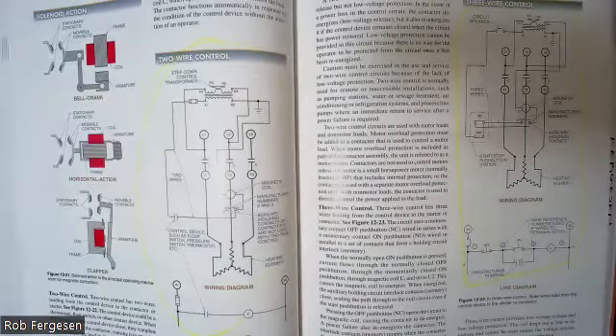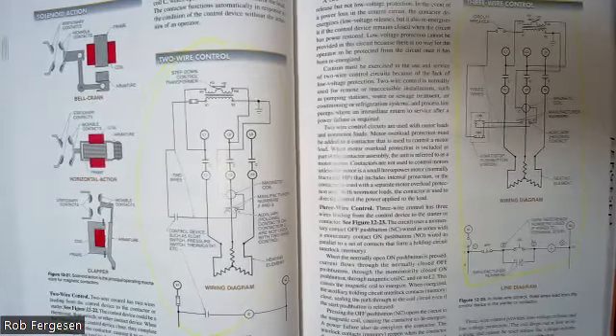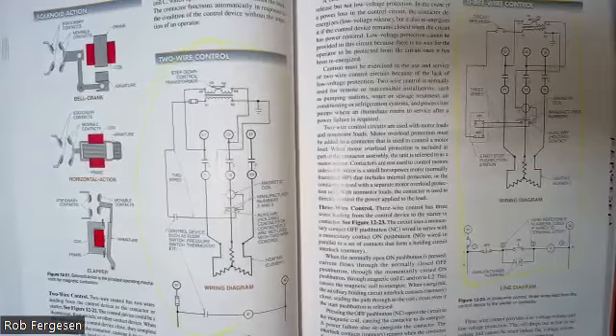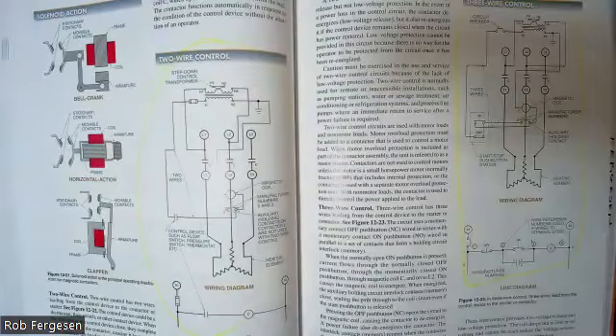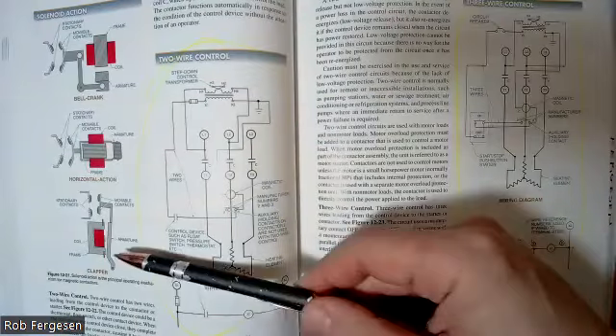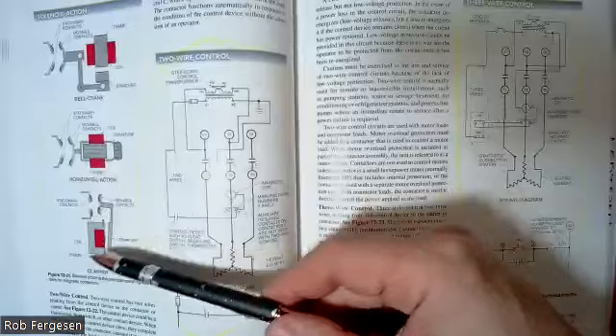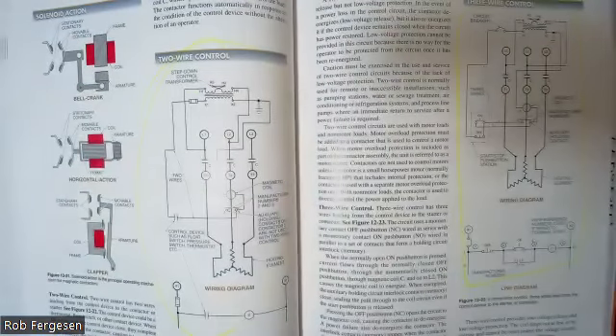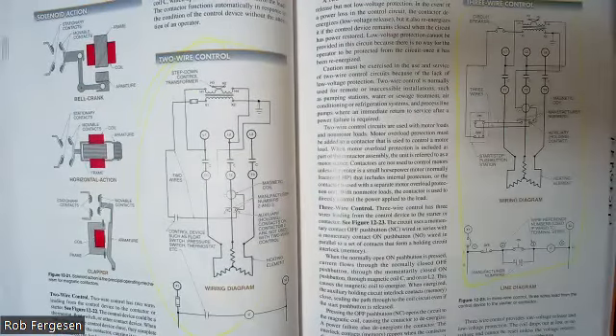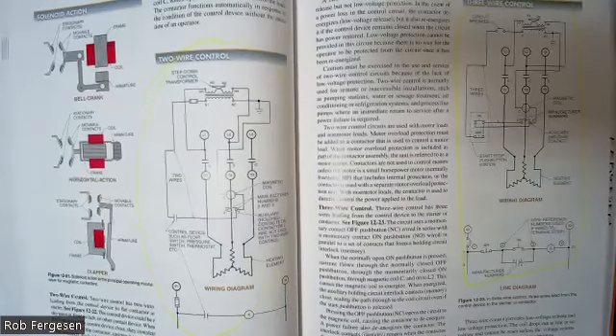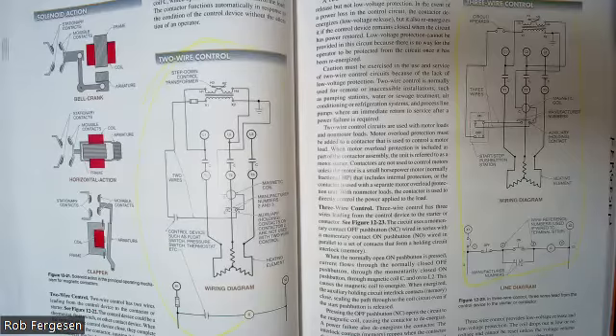Since I generally don't rebuild contactors, I generally throw them out and buy new. Technically, you can rebuild them. The ones I have rebuilt, I basically just replace the contacts or replace the coil. The coils burn out on a regular basis, so they do need to be replaced. But for most contactors, you're just going to buy new.